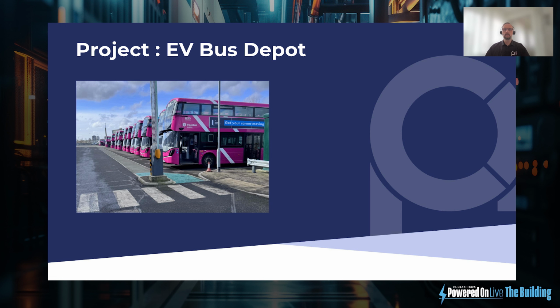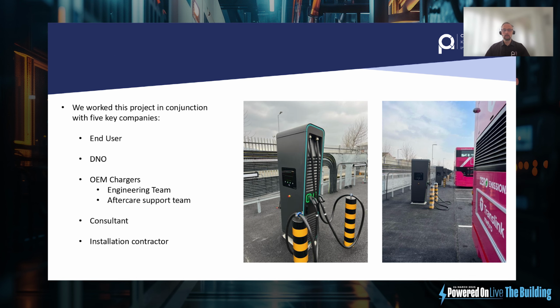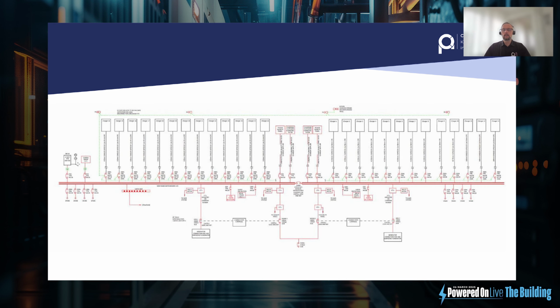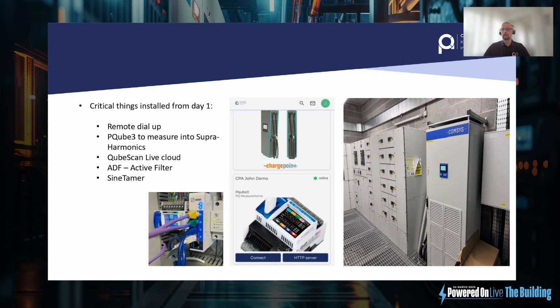So I'll give a couple of examples now as we come into closure on some cases where we helped customers resolve issues from design through to problem solving. So this is a bus depot. We worked with them from beginning to end. We worked with the end user, the DNO, the OEM charger manufacturer, the consultant, and the installation contractor to make sure everyone was unified and united in the approach. We went through their system design, working through what they were trying to achieve. We simulated the harmonic spectrums that they planned to generate. And these are heavily dynamic loads. So even if you do simulate, they're not going to operate anything like what the perfect world is.